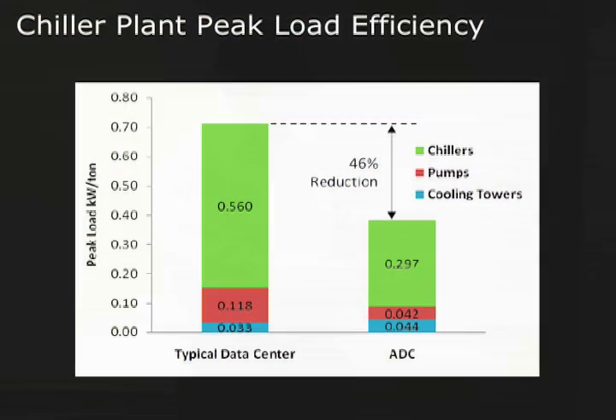Even 60. So the chillers, if you size for that, will be a lot more efficient. And guess what? They'll be cheaper on a dollars per ton basis because the compressor is smaller. So if you look at the kilowatts per ton of the chilled water plant, a typical data center would be, including the pumps and the towers, somewhere around 0.7. And this plant, including pumps and towers, is going to be a little bit under 0.4 kilowatts per ton.